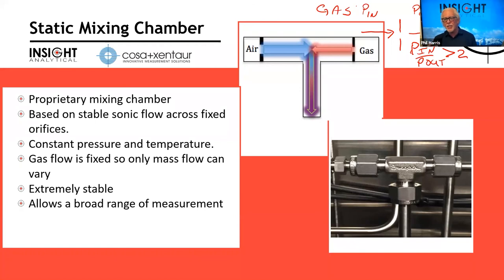Gives us an extremely stable way to make this mixture happen. And that is one of the important things that we need in order to optimize this type of measurement. If we get that stability, even as the fuels change composition, we can get this really broad range of measurement, get good mixing, and get the right air ratios in there so that we can actually make the measurement as we need to. So we get this completely mixed, and then we run it through this furnace.